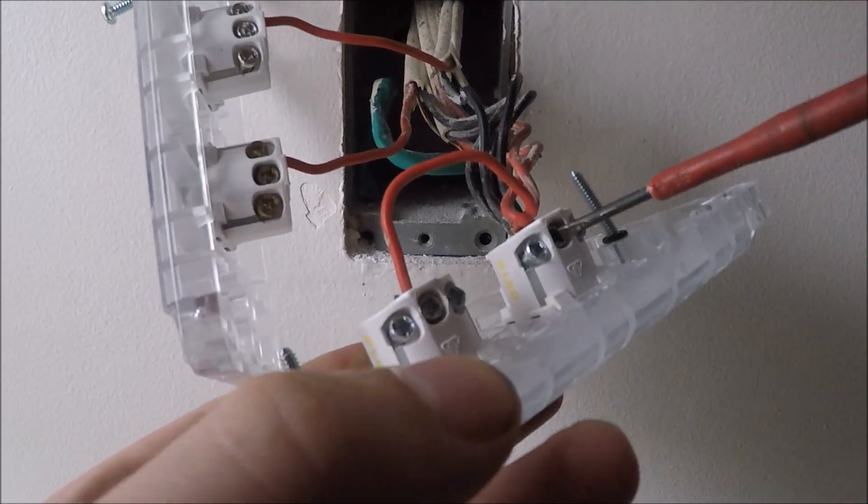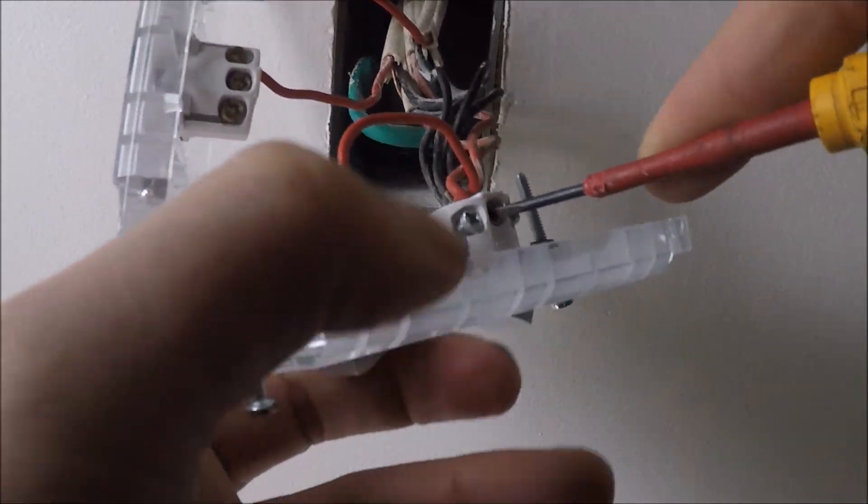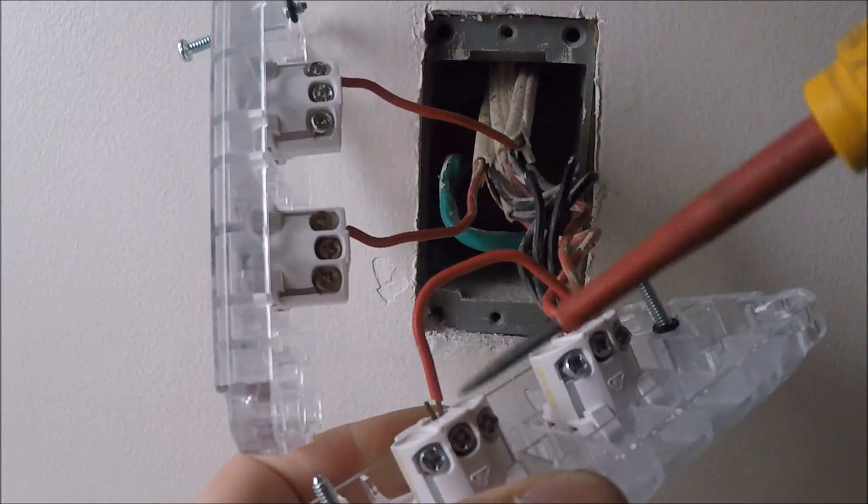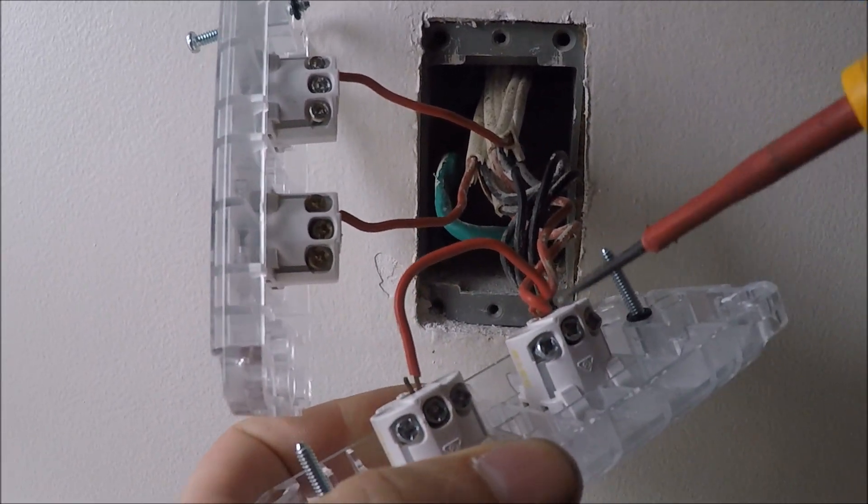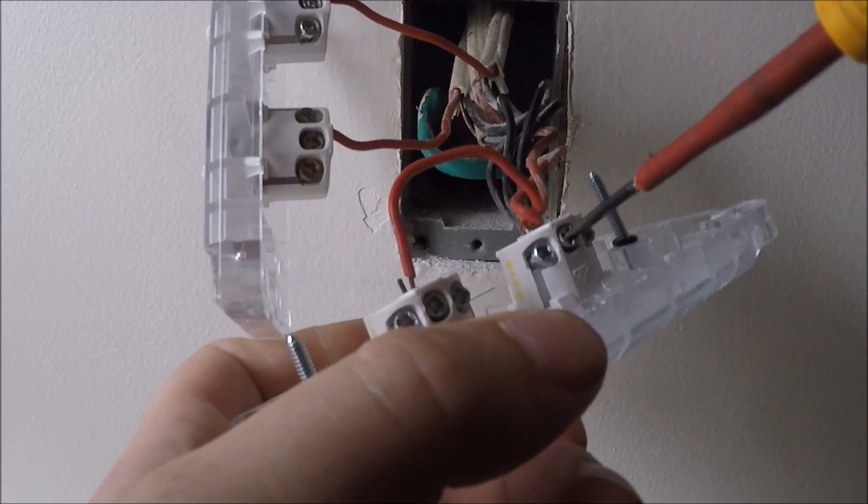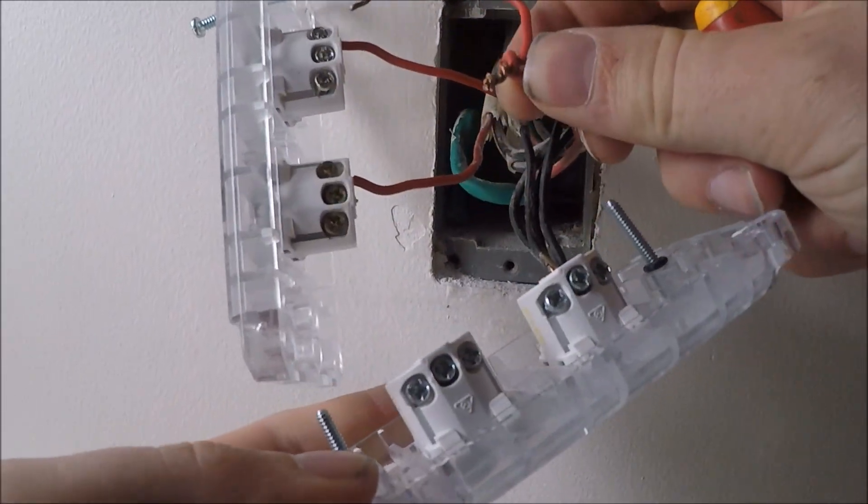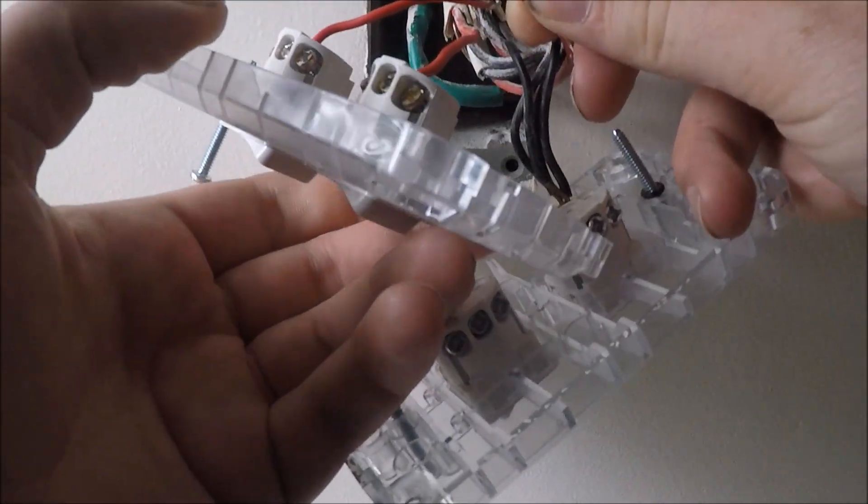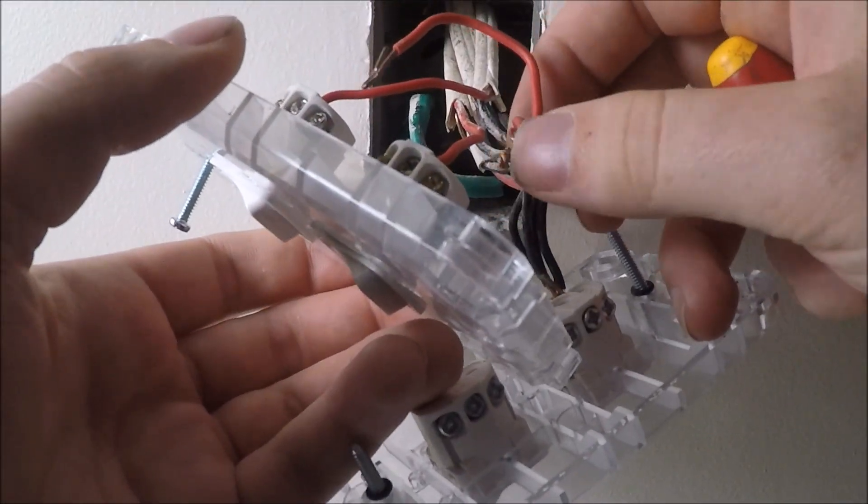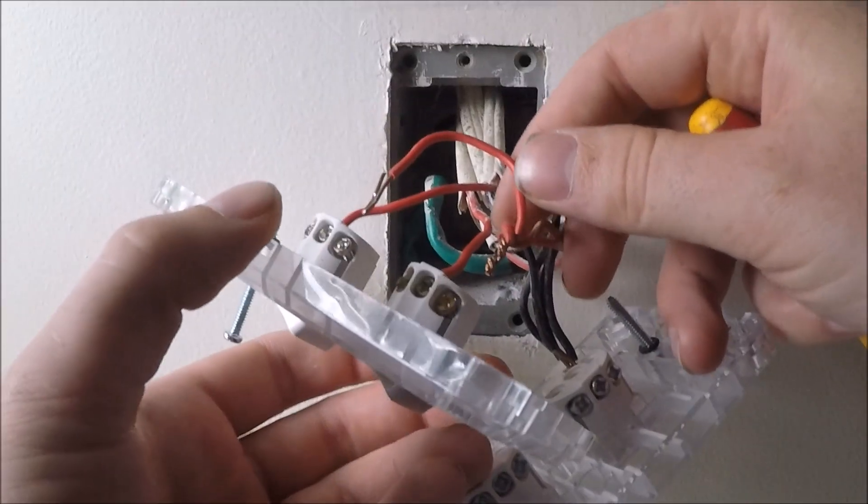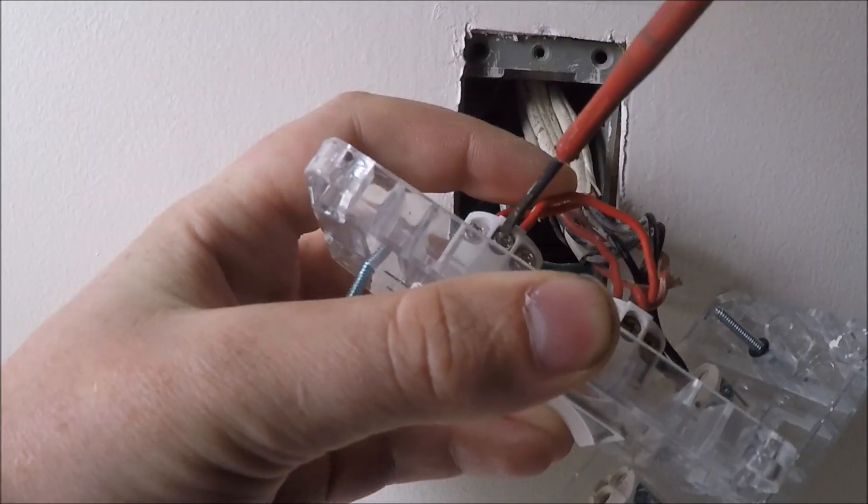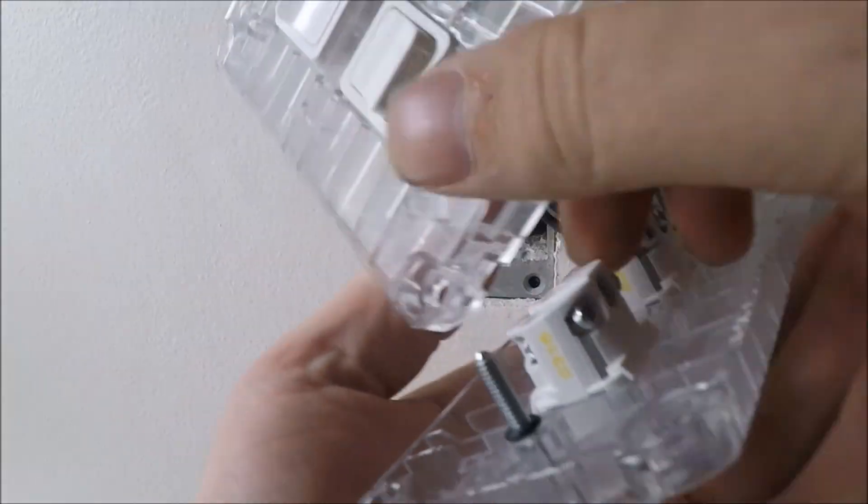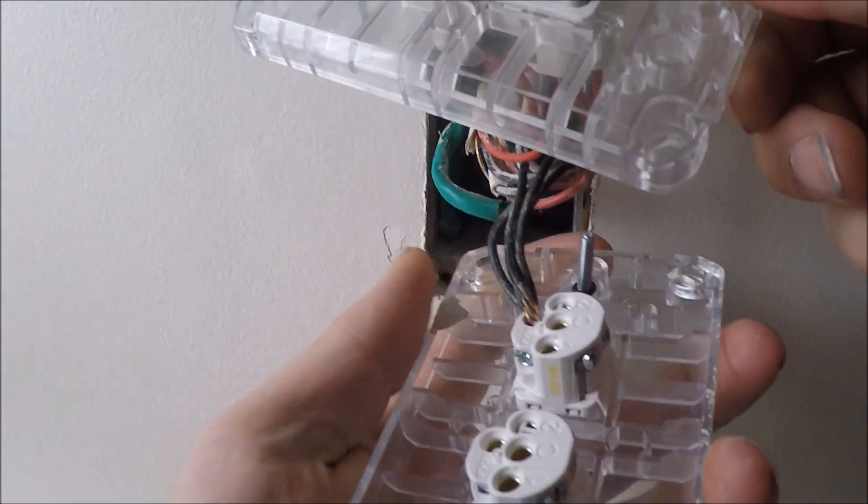Undo both these at once because you'll find the one on the top mech is looped and twisted into the ones on the bottom mech. Pull them out, check they're terminated nicely. They're average but they're not broken so I'll be keeping them as is and then screw them into these mechs. Last of all you'll find that the neutrals and possibly the earths are in loop terminals.